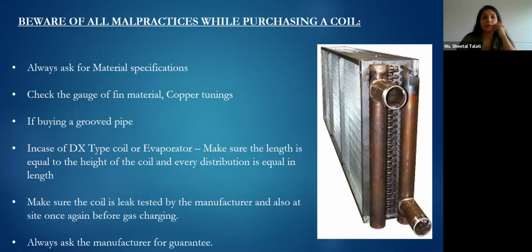Moving on to the malpractices that go around while purchasing a coil. Always ask for material specifications from a manufacturer. What happens is when you ask for 2-3 quotations, you will find a lot of difference between my quotation and another manufacturer's quotation and the third person's. Because the copper prices are very high, the material cost itself is very high, and you can cheat a customer by changing the gauge of the pipe or the fin material. So check the fin material gauge and the copper tubing gauge, whether it's an inner groove pipe, because grooved pipes are way costlier than the plain ones.